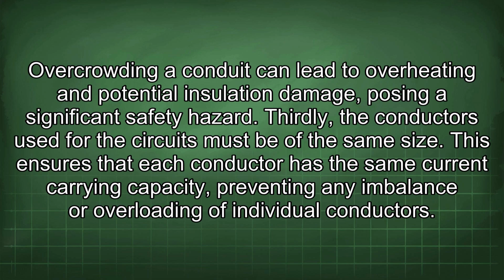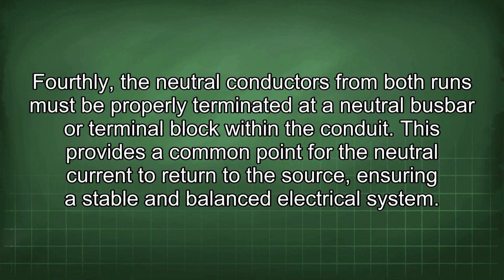Thirdly, the conductors used for the circuits must be of the same size. This ensures that each conductor has the same current carrying capacity, preventing any imbalance or overloading of individual conductors. Fourthly, the neutral conductors from both runs must be properly terminated at a neutral busbar or terminal block within the conduit.